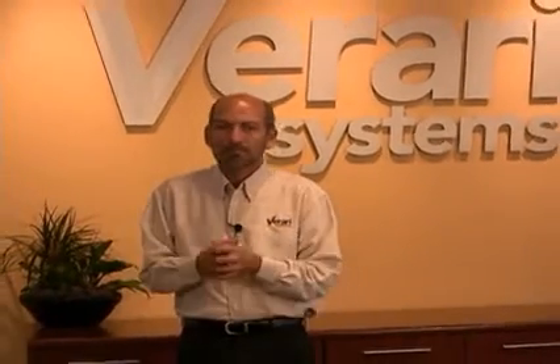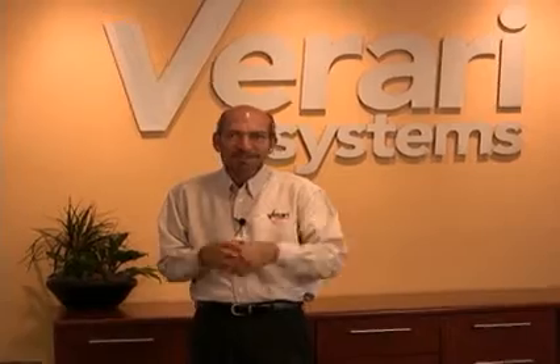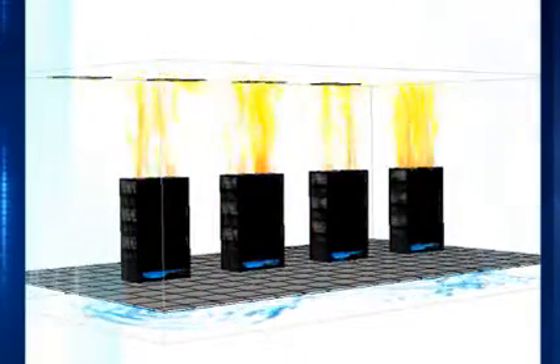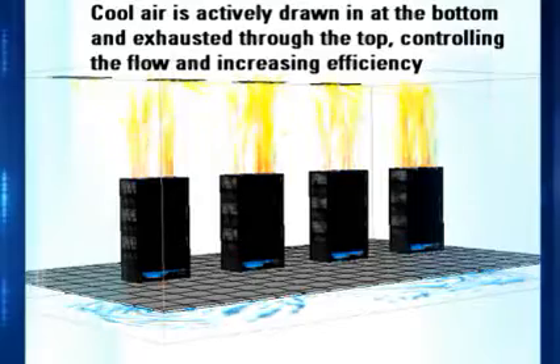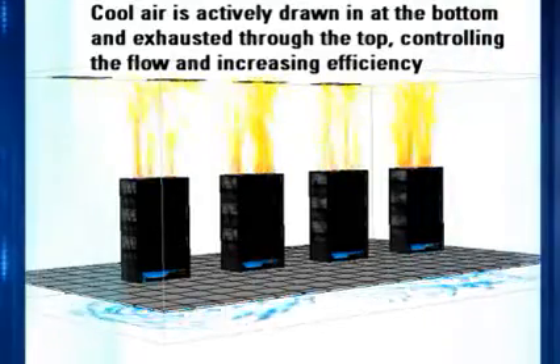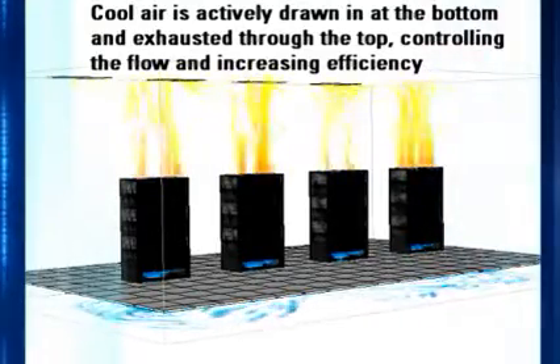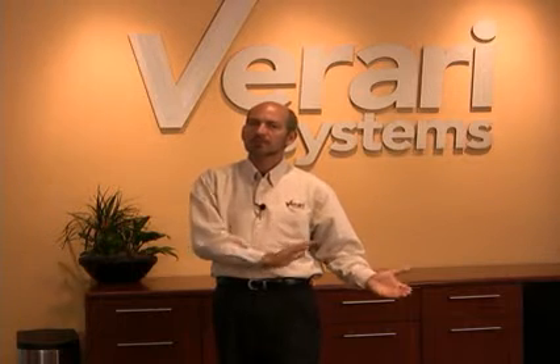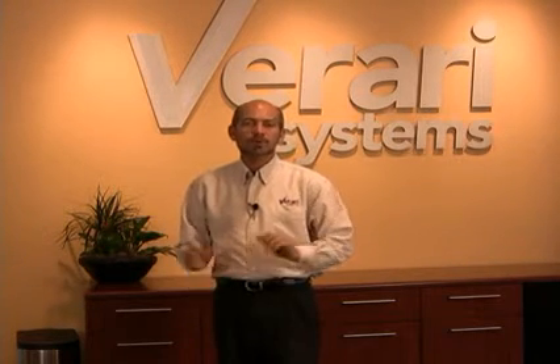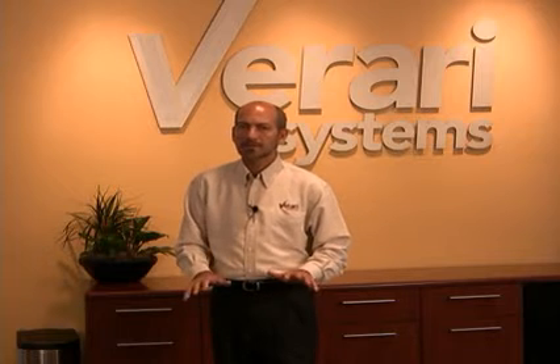Instead, we said, let's get the air from underneath the rack. We've got free square footage there. 2 floor tiles directly underneath the rack where we could actually draw air from. Also, it just happens that the law of thermodynamics says that hot air rises and cold air falls. By taking air in at the base of the cabinet, we were going to actually get the coldest air in a data center. And so we designed our vertical cooling technology. We actively draw air in at the base of the cabinet. Doesn't matter if it's a raised floor or a slab floor, the coldest air in a data center is going to be at the floor.